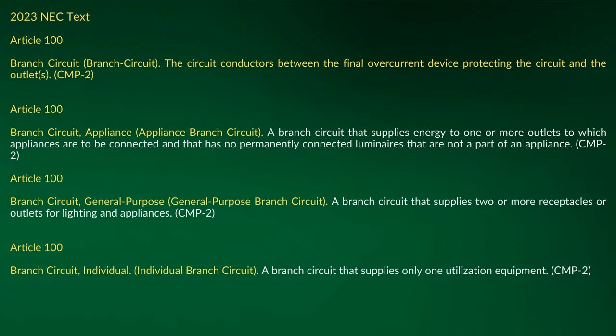Now, we heard over and over about this outlet, blah blah blah, and the AC unit had to have GFCI protection. They lacked technical merit. And actually, it was the TIA that Code-Making Panel 2 wrote that lacked technical merit, and I'm going to prove it right here. It says, in reviewing the full record, the appellants renewed some of the concerns Council has heard in the prior appeal, including the practical impact of yet unresolved interoperability issues between GFCI and HVAC equipment.